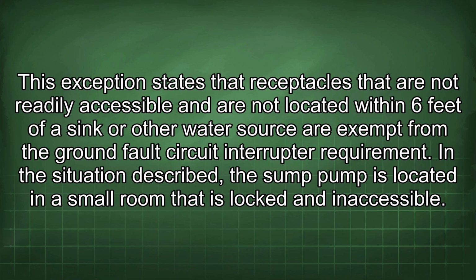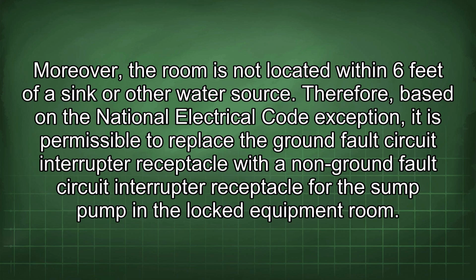In the situation described, the sump pump is located in a small room that is locked and inaccessible. Moreover, the room is not located within 6 feet of a sink or other water source. Therefore, based on the National Electrical Code exception, it is permissible to replace the ground fault circuit interrupter receptacle with a non-ground fault circuit interrupter receptacle for the sump pump in a locked equipment room.